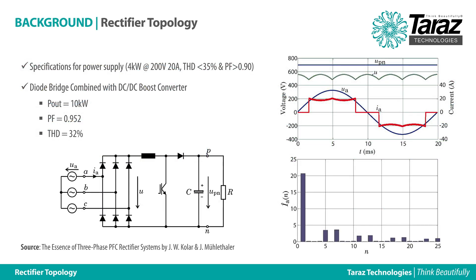The active rectifier under test is part of a programmable DC power supply. The topology used is a diode bridge combined with a single boost converter. A low number of components make this topology cost-effective with a decent power factor of 0.952. However, the input current is non-sinusoidal, which results in a high total harmonic distortion of around 32%.